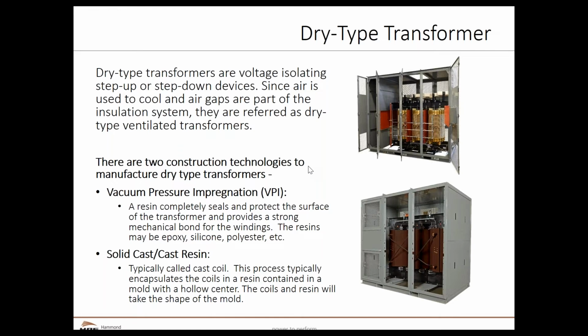The other type is what we call solid cast, where the core and coil is actually put into a mold, and the entire mold is filled with an epoxy resin and hardened. This provides a much thicker coating. In the other one, the VPI portion, the majority of the insulation system really is based upon air gaps. When we do the cast resin, the great majority of the insulation system is really based upon the resin material itself. In some ways, it's more analogous to a liquid filled transformer, but again, there are very different constructions and performance.